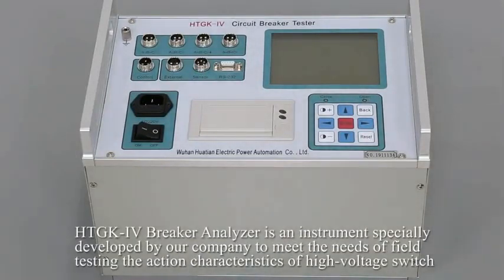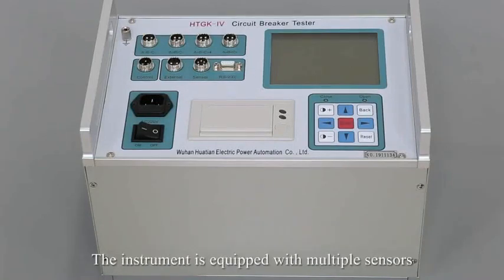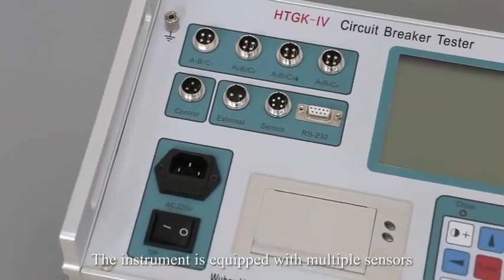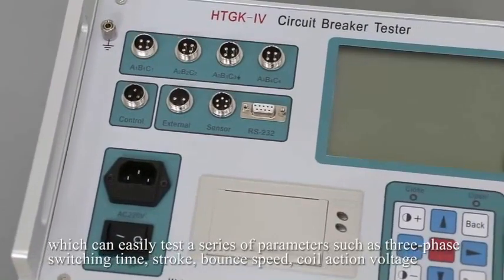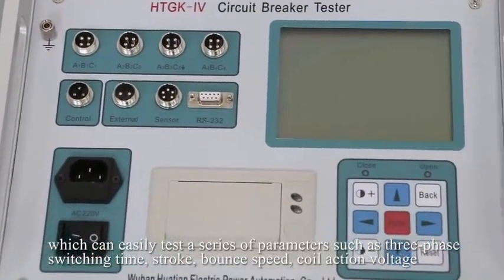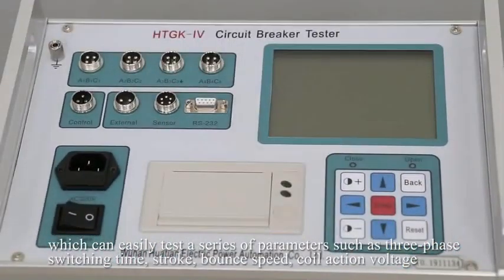The HTGK IV breaker analyzer is an instrument specially developed by our company to meet the needs of field testing the action characteristics of high voltage switches. The instrument is equipped with multiple sensors, which can easily test a series of parameters such as three-phase switching time, stroke, bounce, speed, and coil action voltage.